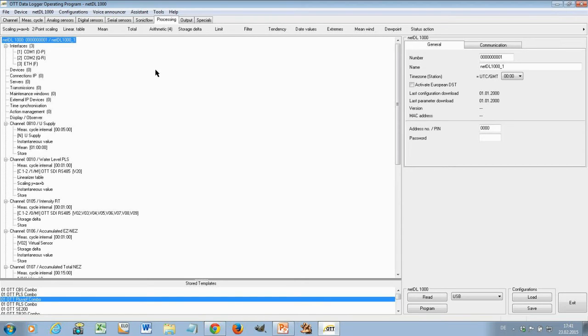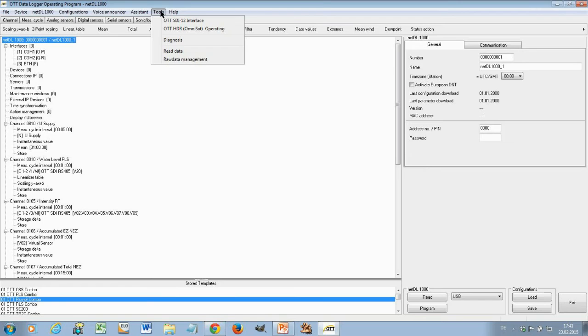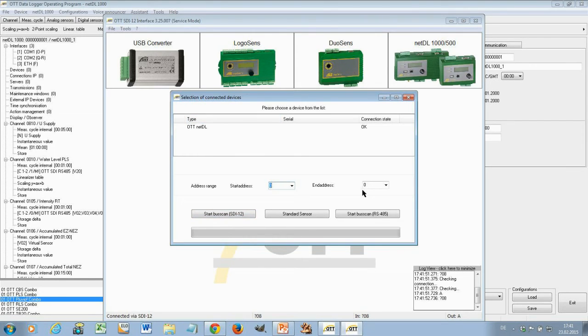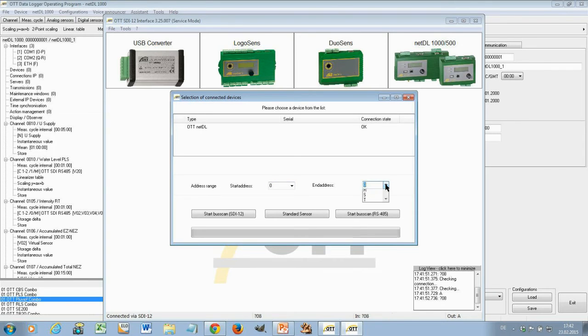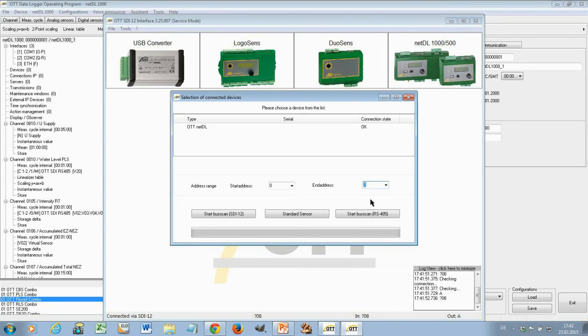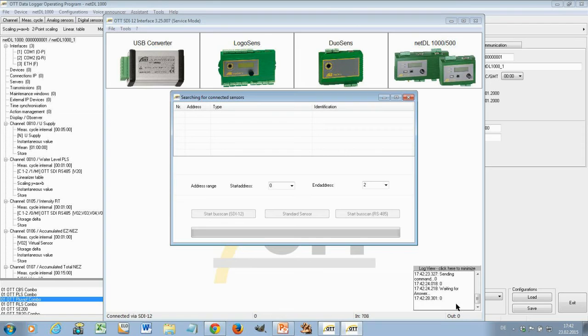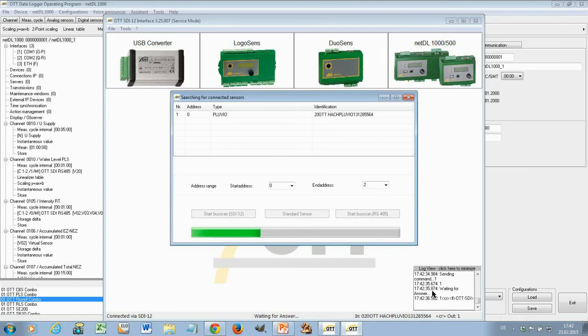Another tool which helps you to work with sensors is the so-called SDI-12 Interface Module. The SDI-12 Interface Module can be also found under Tools, OTT-SDI-12 Interface. If you click on that, the tool finds now the OTT-NetDL. And now you can scan the data logger regarding sensors. If you don't know the SDI-12 addresses of your sensors, you can scan here the whole range of addresses. I know that my sensors are in the range between 0 and 2. So, I'll scan only this range because that goes faster. And I know also that this is a RS-485 SDI-12 sensor. So, I press here now Start Bus Scan.